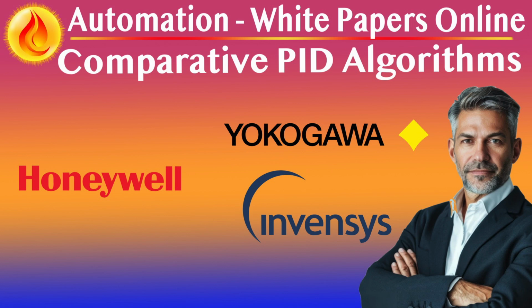Cascade, feed-forward, and constraint logic. Honeywell provides native cascade and override structures inside its PID and logic blocks. Mode tracking, setpoint propagation, and reset feedback are internally managed, making configuration clean, modular, and efficient. Feed-forward paths can be enabled directly within the PID block, with scaling and biasing handled through intuitive parameters.